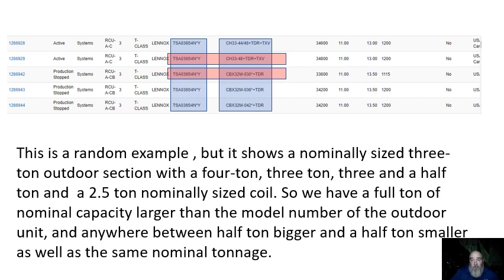This was just a random selection that I did here. I'm looking at two systems here, which happen to be a 3-ton or 036 outdoor unit, and they're showing it matched in this instance to AHRI. The verbiage below explains how I randomly picked an example from the AHRI website that shows a nominal 3-ton outdoor unit, and in this pairing, it's matched to a nominal 4-ton coil.